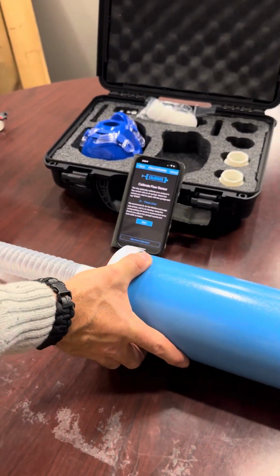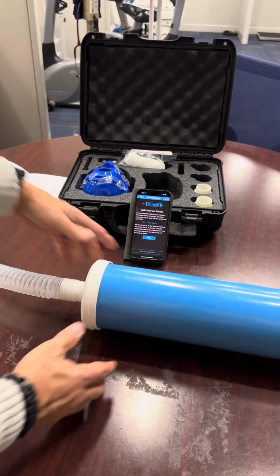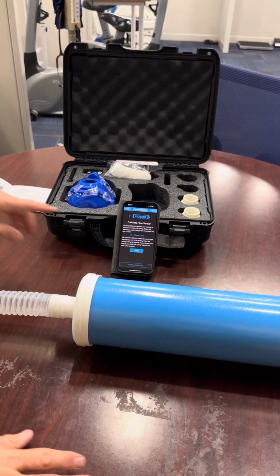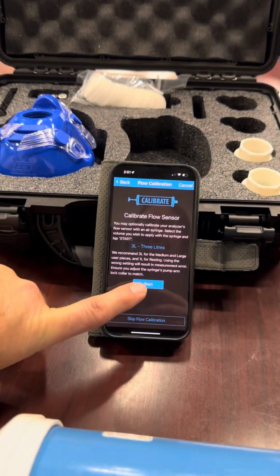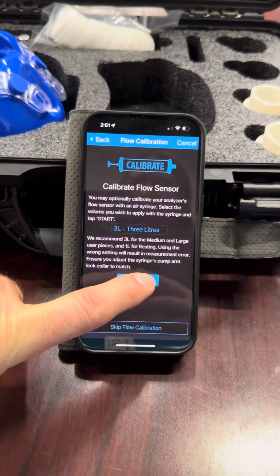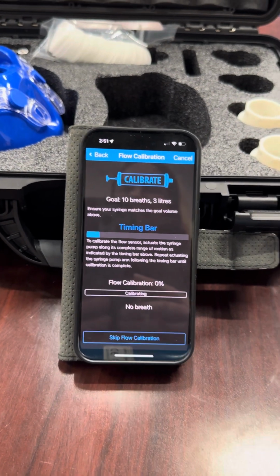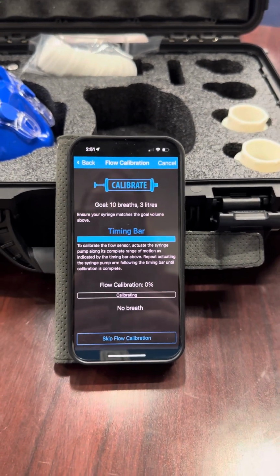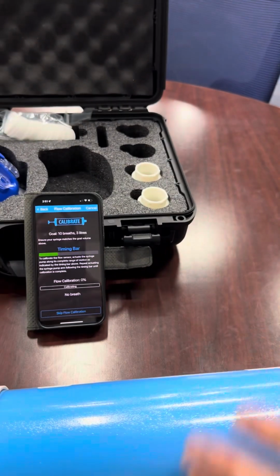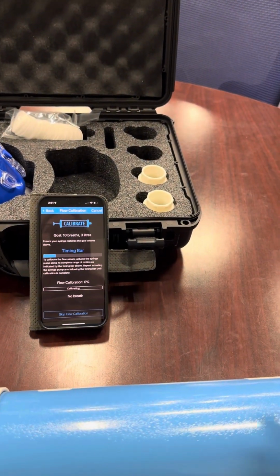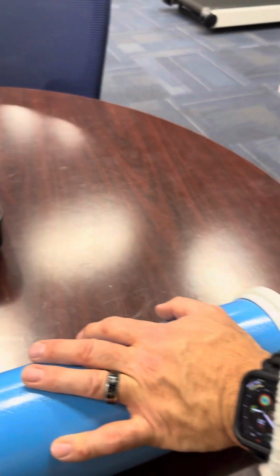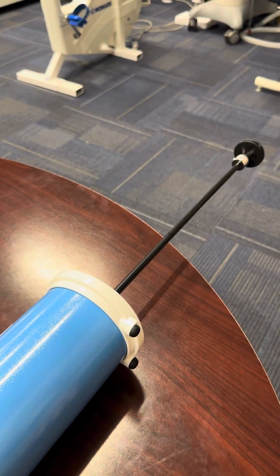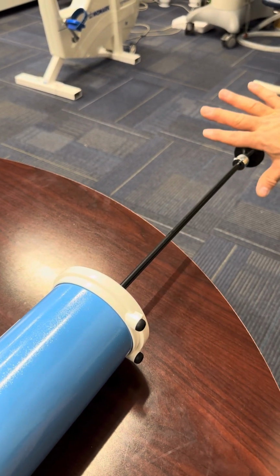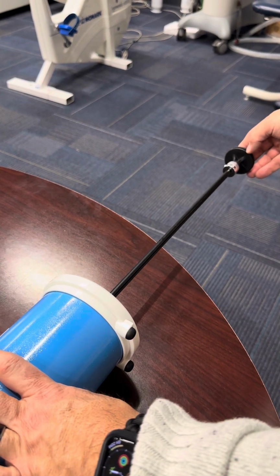Okay, so now we are pretty much ready to roll to do the calibration. If we look up at the calibration, up at the phone, it says start. So we want to hit start, and then there's a timing bar. We want to make sure we do in and out with the syringe according to what it says. Every time it goes blue, that is when there's an exhale. Is that correct? Yep. So I'm just going to pull it out just to get it all ready to go. So we've got this syringe out. It is already exhaled. No, it's already inhaled. So on the exhale, I want to make sure it's blue. So right now, blue.